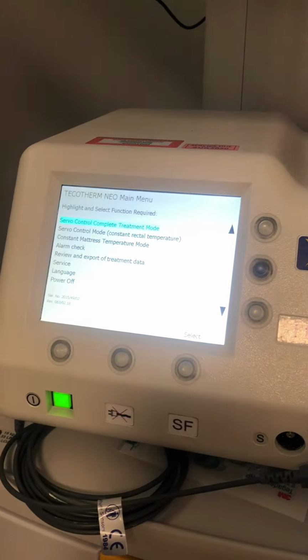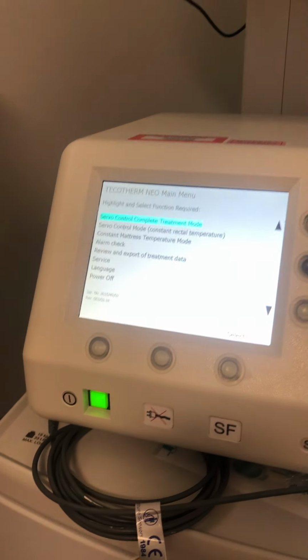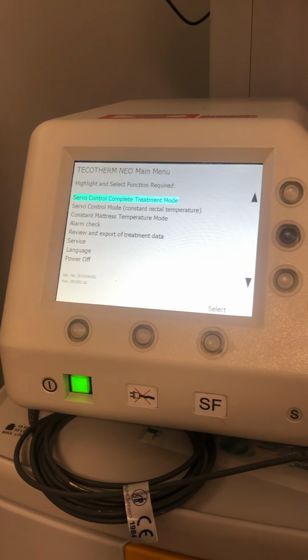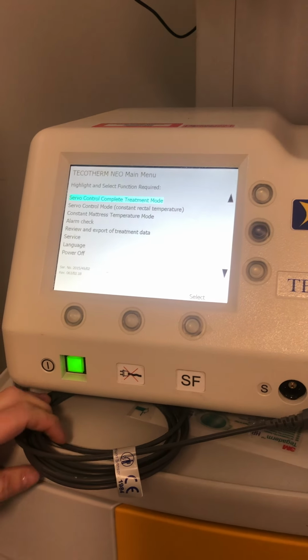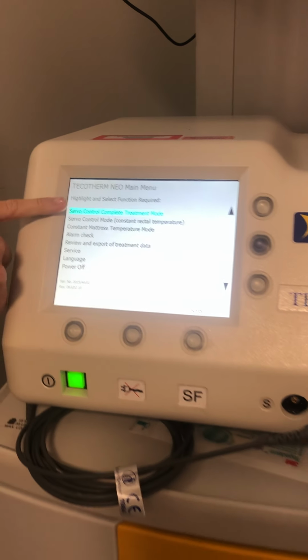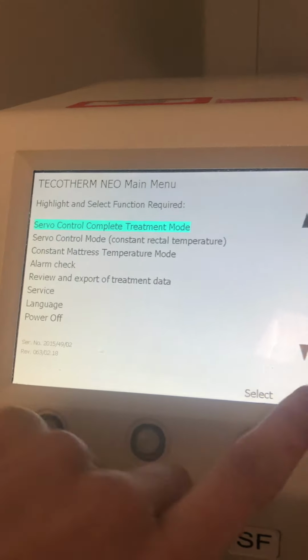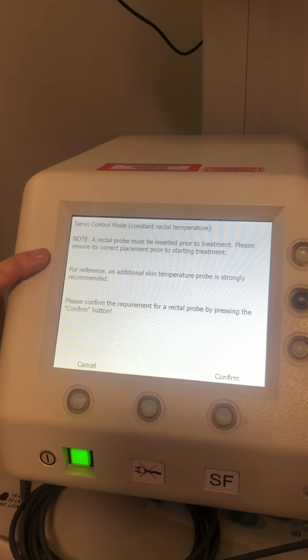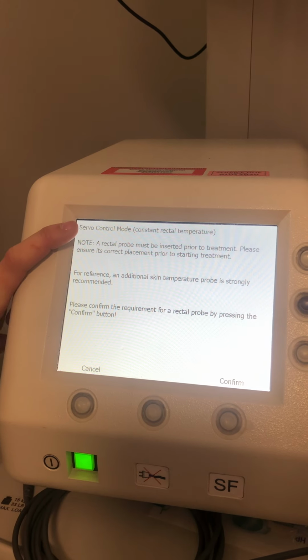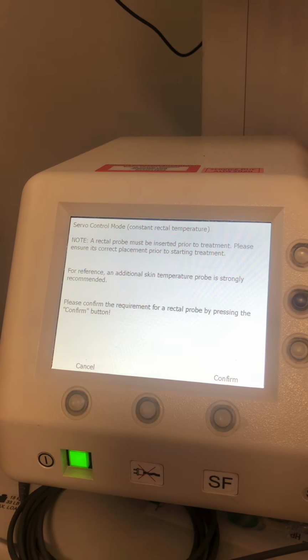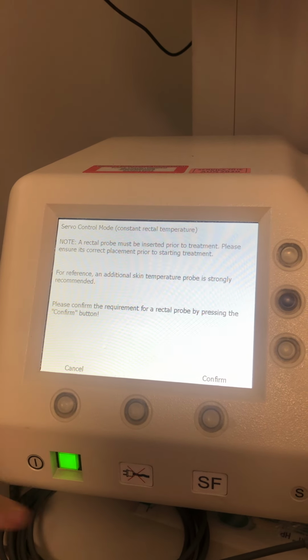Once you're happy that the mattress is full, at this point you can't do anything until you've got the baby. So once the baby arrives, what you're going to be using is the servo control mode, constant rectal temperature. So go down and select. In this mode, the first thing it's going to tell you is you need a rectal probe. So you can't use the cooling mattress on a baby unless you've got a rectal probe in.